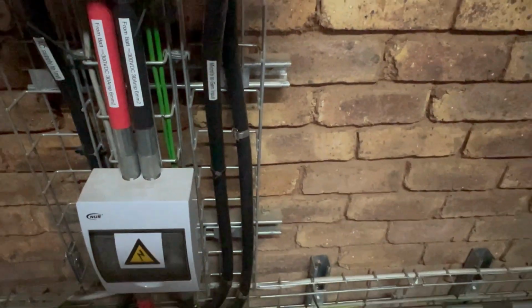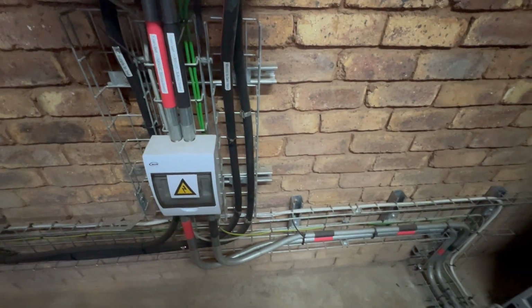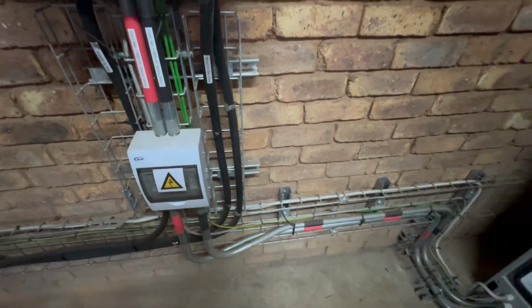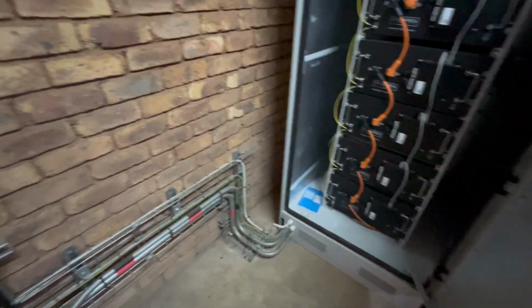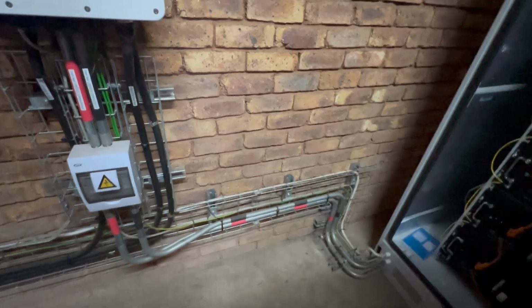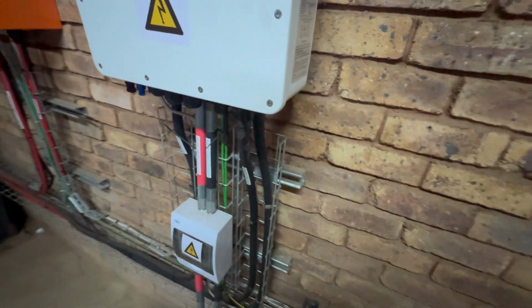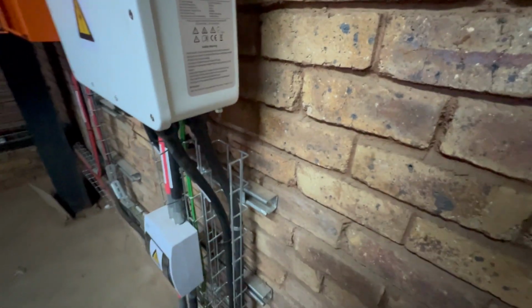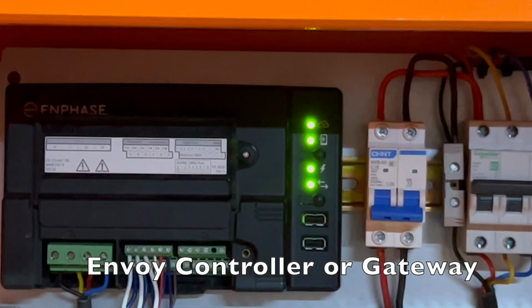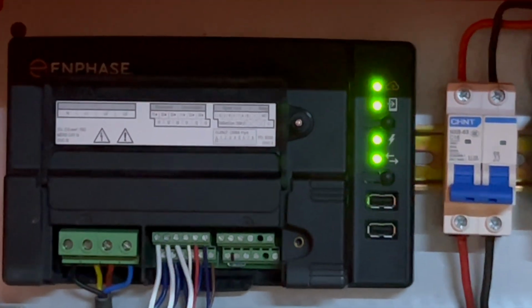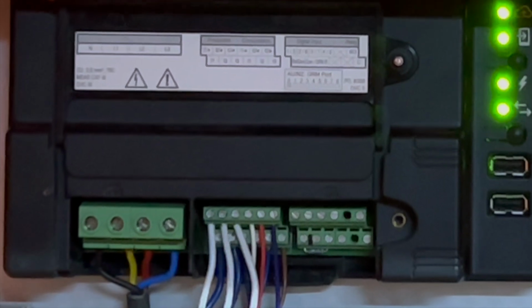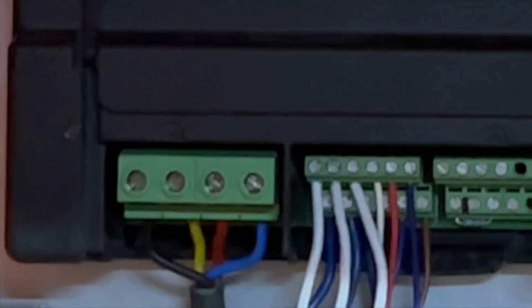I personally think it's a bit of an overkill, so we just did a couple of those because the cable that we're using over here is only 16 millimeter 4-core cable. Even the cable is a bit oversized, but that's the cable we had in stock, so we decided to use it in any case. One of the issues was that the supply for the Enphase controller is supposed to have the same phase sequence as the site.